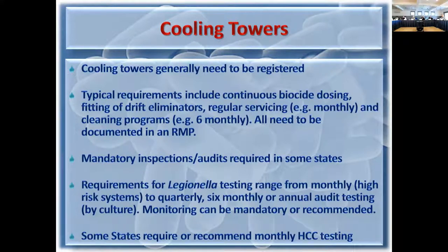So, cooling towers. In most jurisdictions, cooling towers need to be registered. Typical requirements in the legislation include continuous biocide dosing, fitting of drift eliminators, regular servicing, and regular cleaning programs. All of these need to be documented in a risk management plan. In some states, we have mandatory inspections and audits required, and then reports have to go to the regulator.